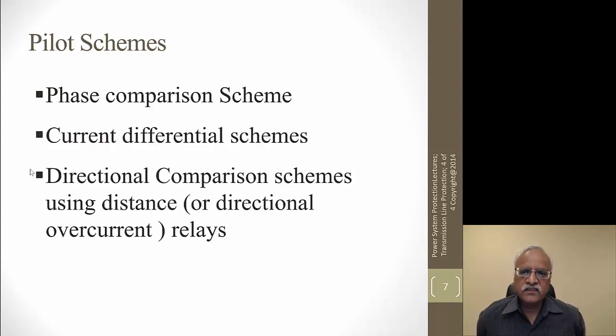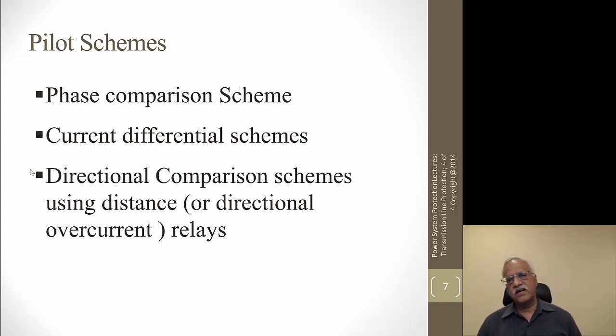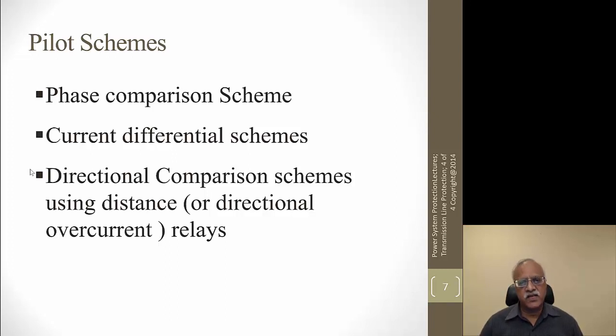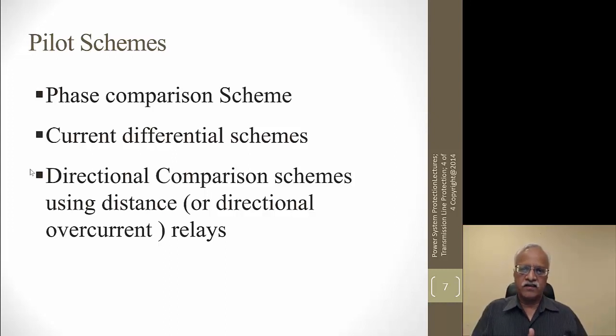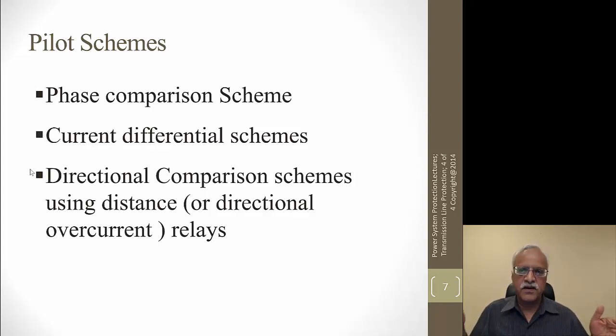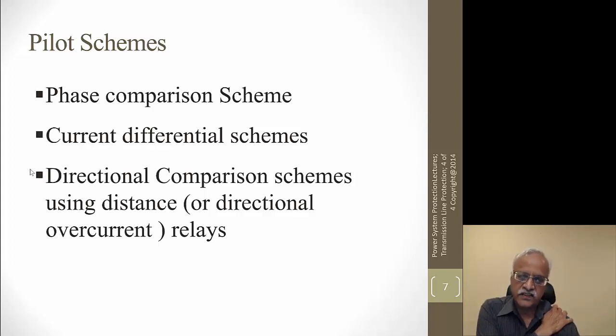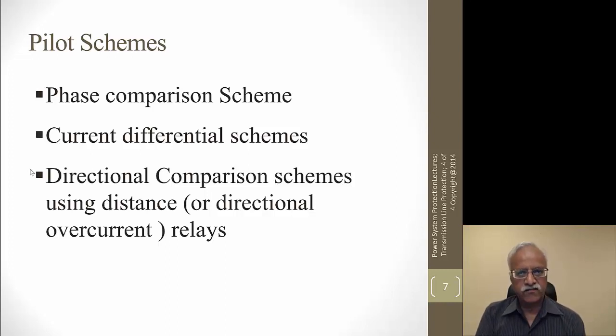Looking at other schemes: phase comparison schemes look at the current coming in and leaving at the remote terminal, check the phase relationship between those two, and exchange information on a communication medium. They can cover 100% of the line section because there is no local 15% or remote 15% uncertainty — it is a differential-type scheme. It can operate instantaneously without any time delay for any fault on the line. Similarly, current differential schemes also provide instantaneous clearing for any fault on the line.